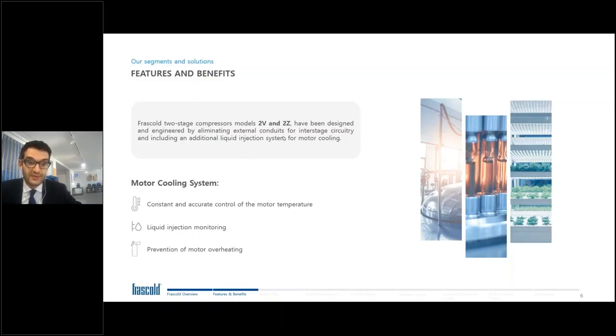In addition, we have a special motor cooling system that has been designed to give a fresh cooling of the motor only when there is the need. So it's a prevention for motor overheating, but the motor is not constantly cooled down by refrigerant, only when it's needed. There is a system that checks the internal motor temperature and decides to open or not the valve in order to cool down the motor if it's necessary.